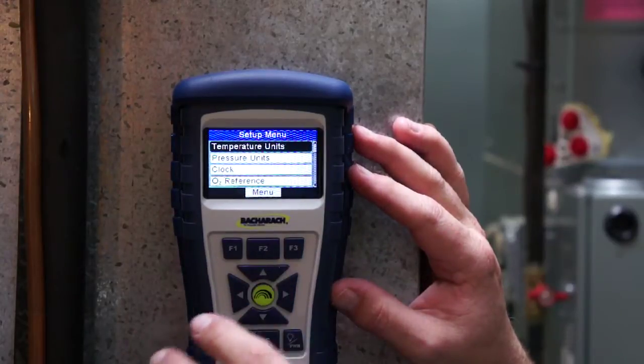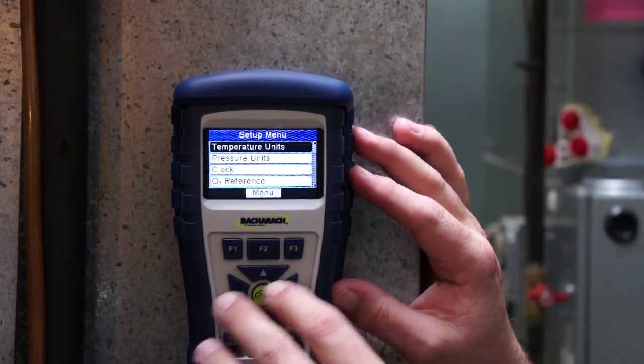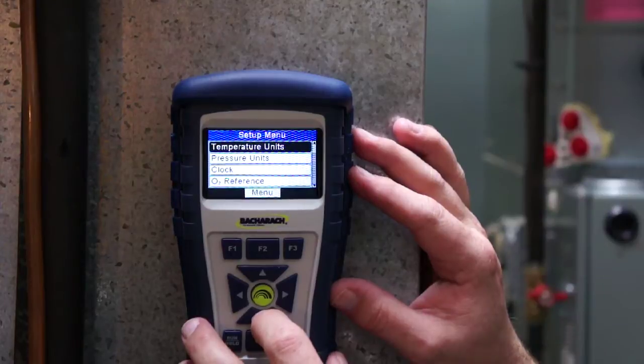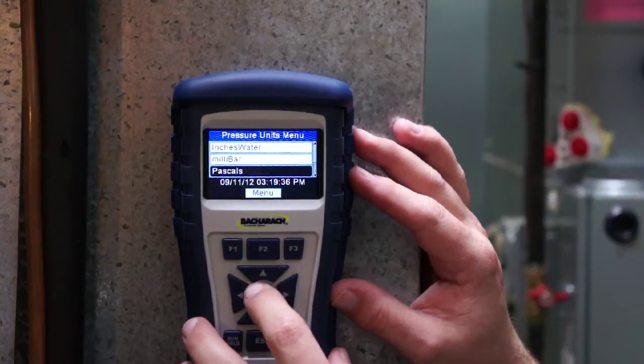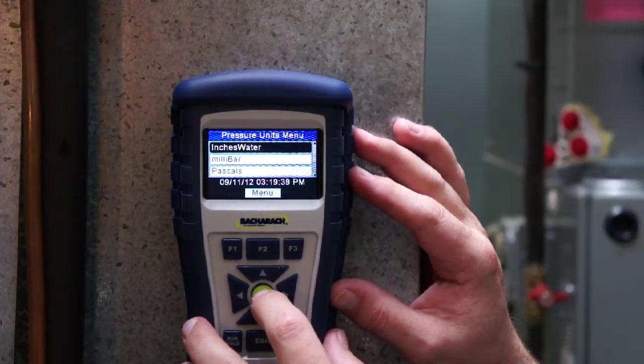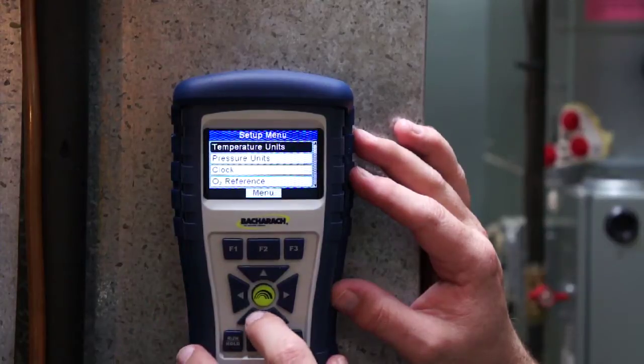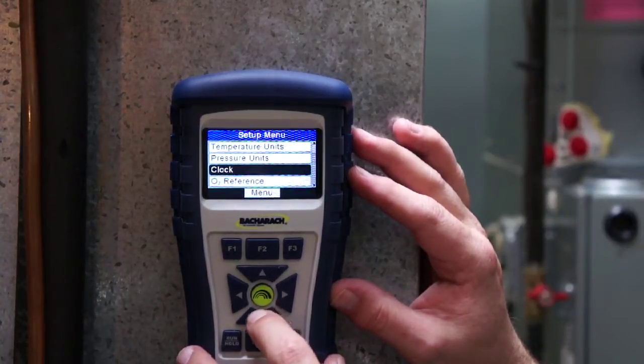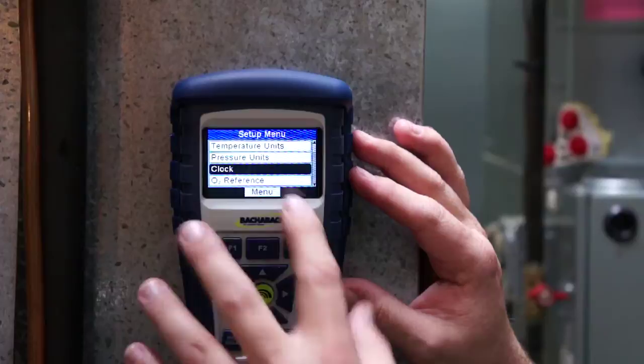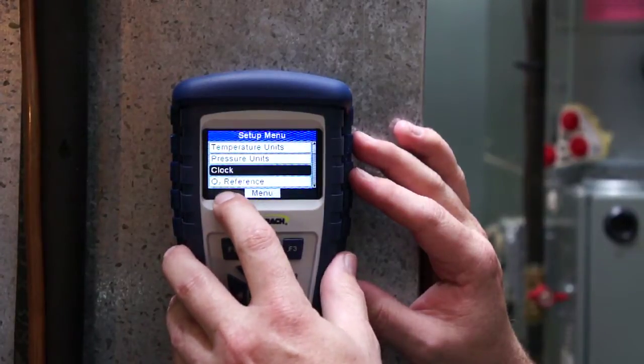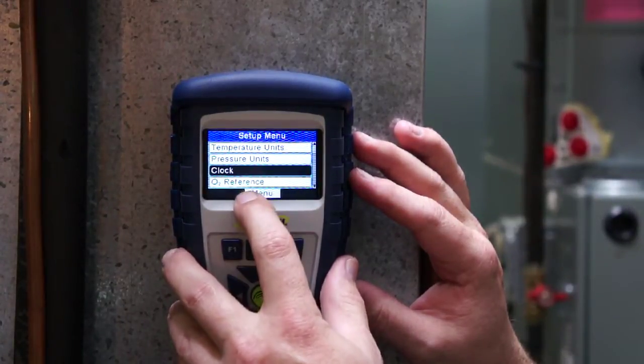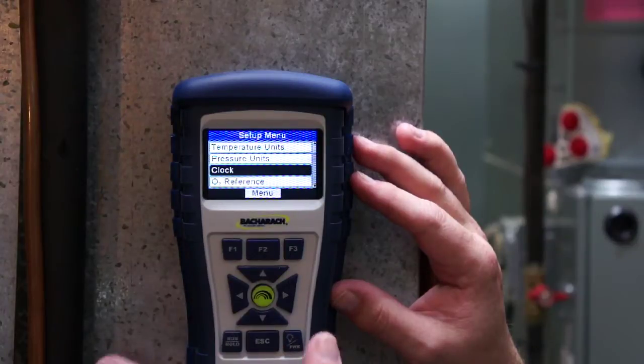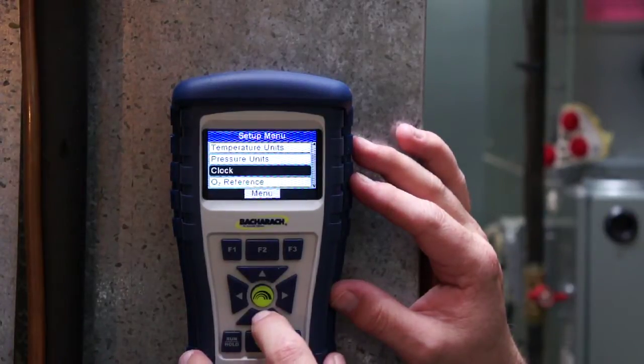As soon as you hit enter, it goes back to the setup menu so you can configure the next piece you want. Now I'm going to work back in inches of water column, so I'm going to go ahead and flip that back up to inches of water, hit enter, and it's configured. Now, I can configure the clock, hours, minutes, seconds, however I want to configure my clock so it reads the way I want it to read. I can configure my O2 reference, which is typically used for European standards, so for most of us here, we're not even going to deal with that.